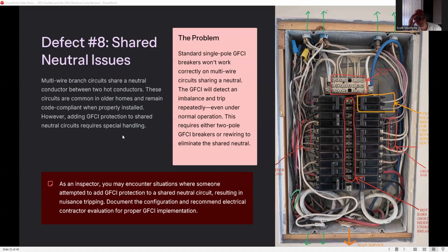The problem: standard single-pole GFCI breakers won't work correctly on multi-wire circuits sharing a neutral. The GFCI will detect an imbalance and trip repeatedly, even under normal operation. This requires either two-pole GFCI breakers or rewiring to eliminate the shared neutral.